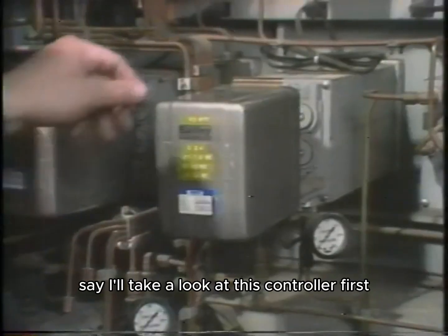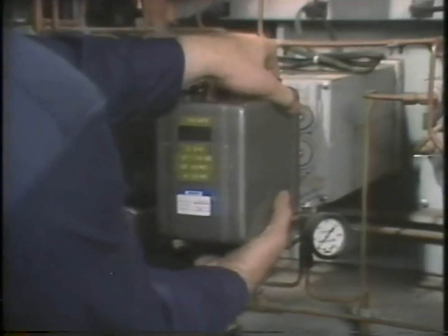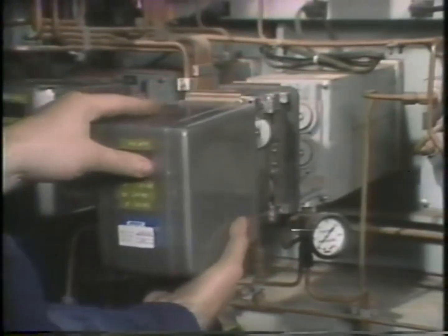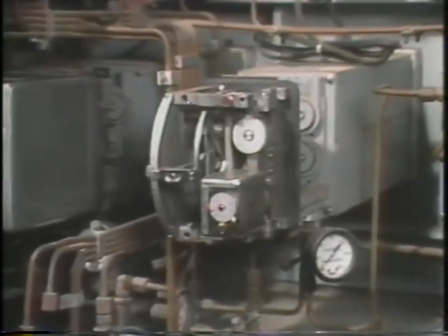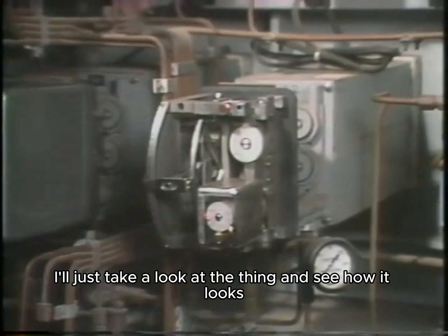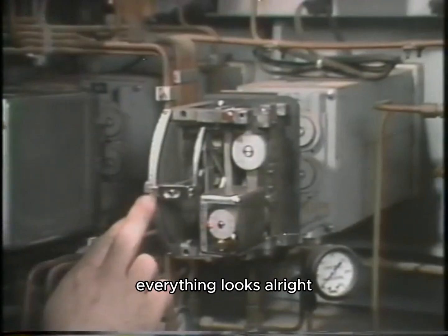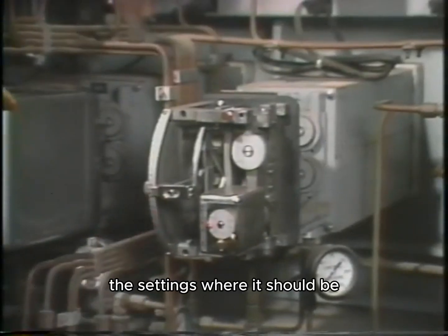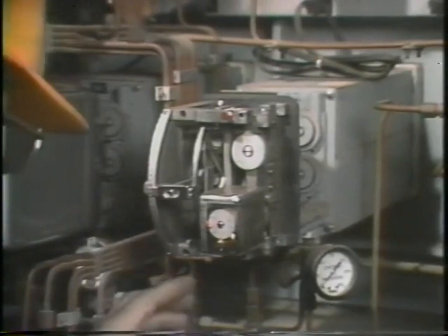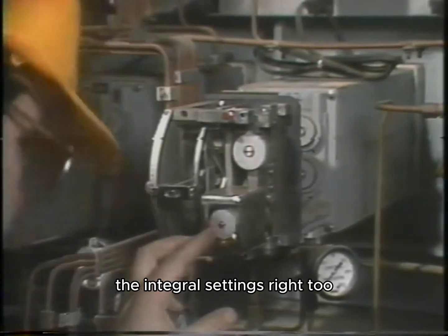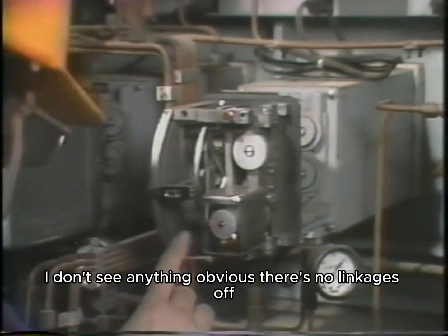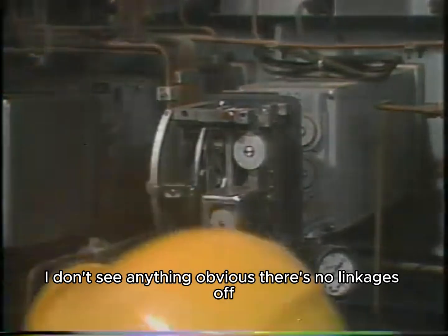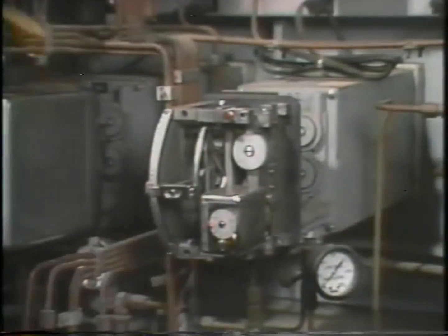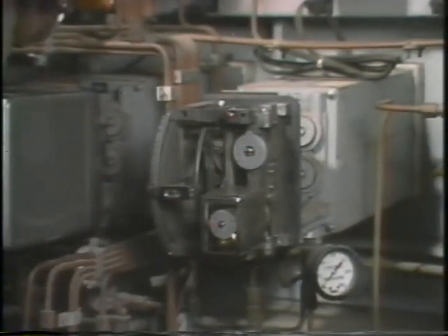Let's see. I'll take a look at this controller first. I have to get the cover off. There. I'll just take a look at the thing and see how it looks. And I don't see any problems. Everything looks all right. The setting's where it should be on the proportional band. And the integral setting's right too. I don't see anything obvious. There's no linkages off. Seems to be working all right.